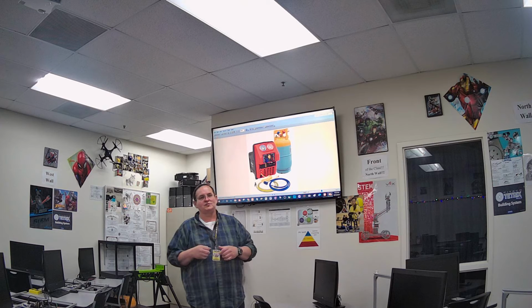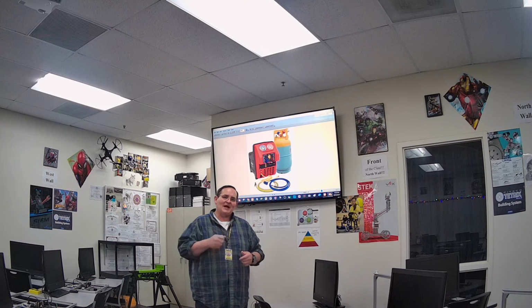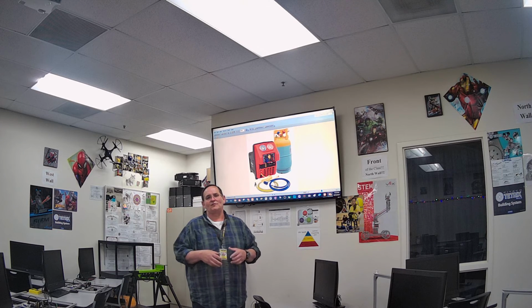You also can use a passive recovery device container, which is like a plastic bag that's designed to put refrigerant in it to help speed up or get as much refrigerant out of the system as you can. You can use a rubber mallet to bang on the compressor a little bit without damaging it, to try to shake up the oil and refrigerant to get the refrigerant out of the oils.